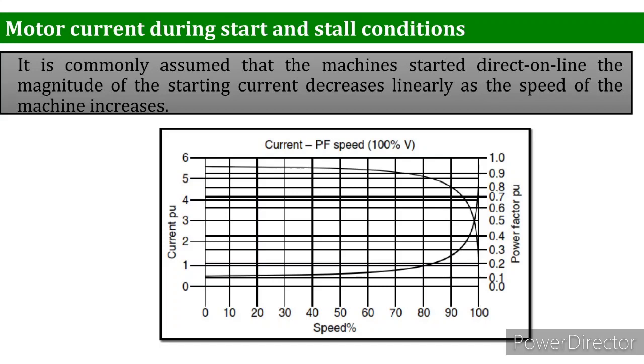So you can see, like I said earlier, in the 80 to 90% or 90 to 100% range there is a little bit of change, but from 0, 10, 20, 30 and 40% there is no change. So this is the basic concept of motor current during start and stall conditions.